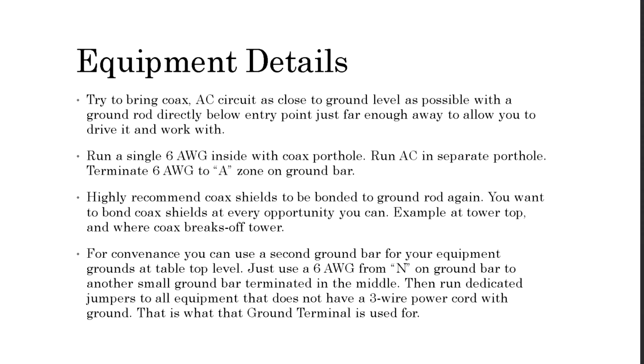Okay, and for your convenience, you can use a second ground bar for your equipment grounds at tabletop level. In other words, you can put a ground bar outside with the surge protectors if you want, and then just run your coax in along with your 6 gauge, and that 6 gauge will come up to another ground bar that you can just use strictly for your station ground to ground your equipment to. Okay?